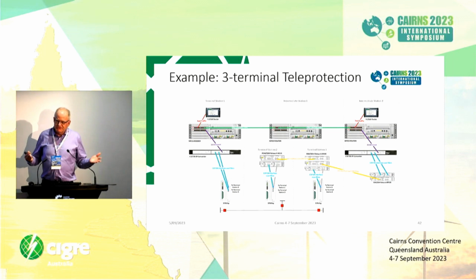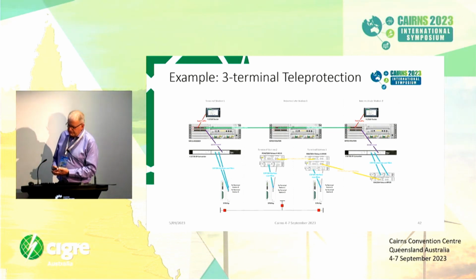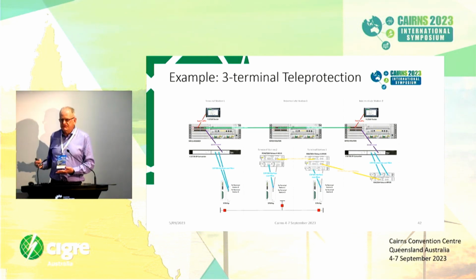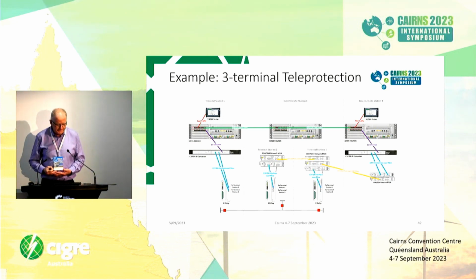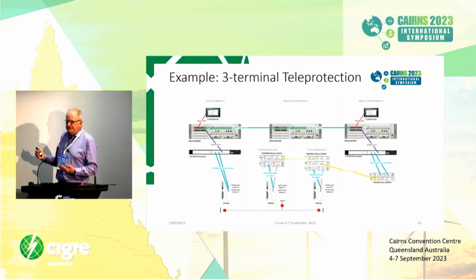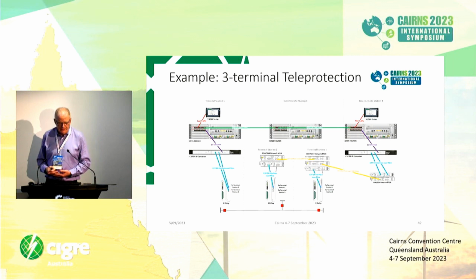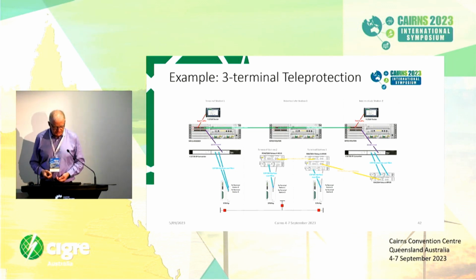The reason why this is so complex, obviously with protection, we try to have diverse paths for our X and Y protection. So this is the X protection setup that uses the diverse path, which goes the long way around the network, if you like. The Y protection uses, in this instance, direct fibre, dark fibre actually, on the transmission line itself. So we've tried to go the long way around to avoid any, I guess, common mode failures. If that fibre were to break, we don't want to take down both the X and Y protection.